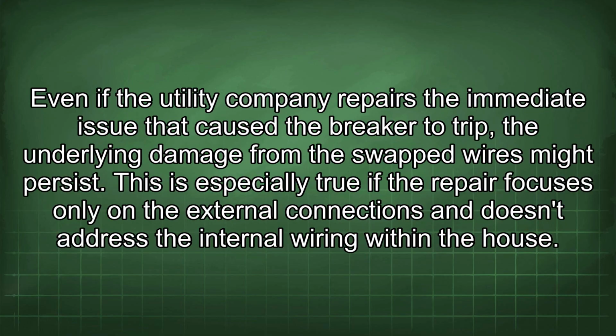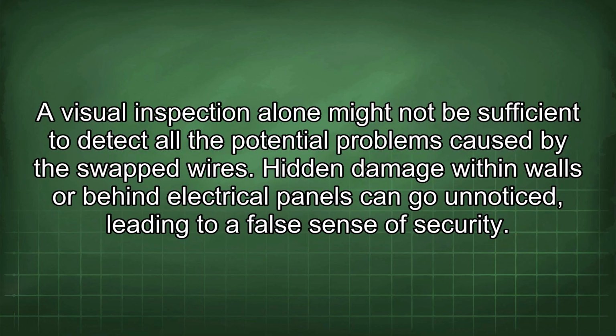Even if the utility company repairs the immediate issue that caused the breaker to trip, the underlying damage from the swapped wires might persist. This is especially true if the repair focuses only on the external connections and doesn't address the internal wiring within the house. A visual inspection alone might not be sufficient to detect all the potential problems caused by the swapped wires. Hidden damage within walls or behind electrical panels can go unnoticed, leading to a false sense of security.